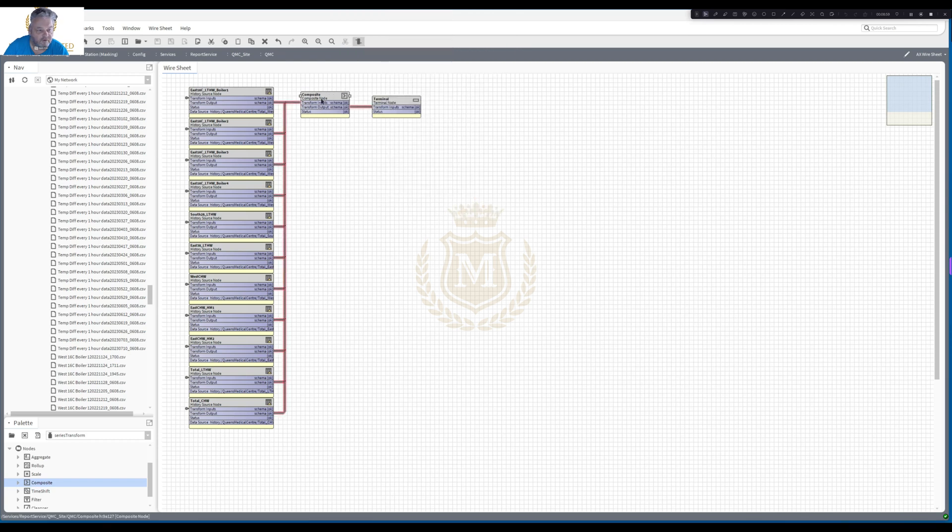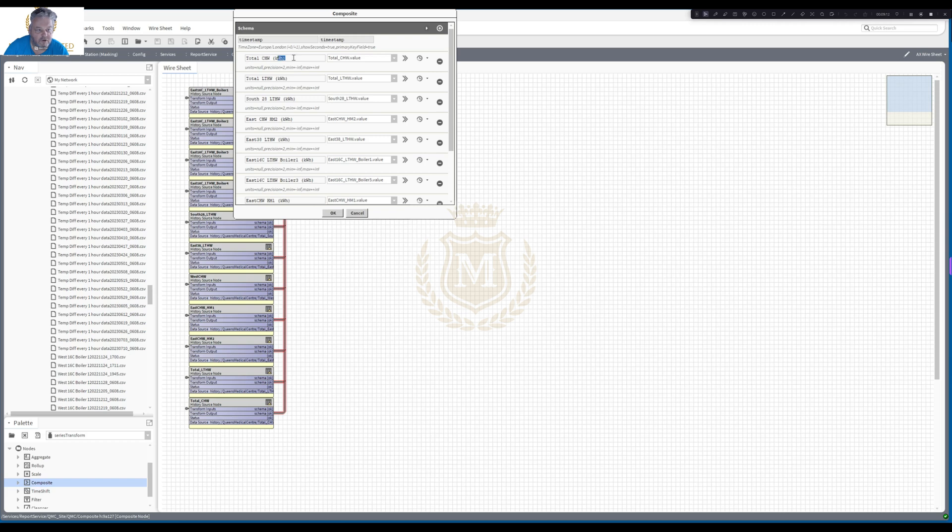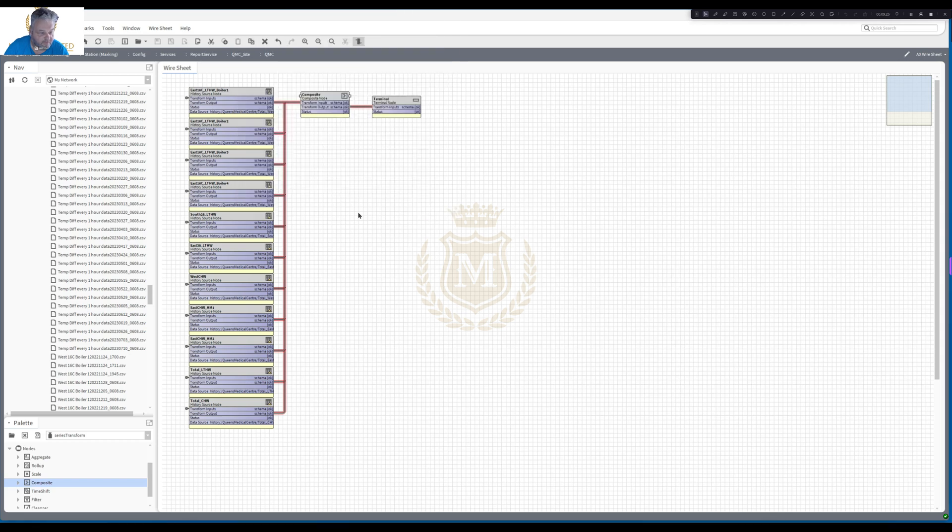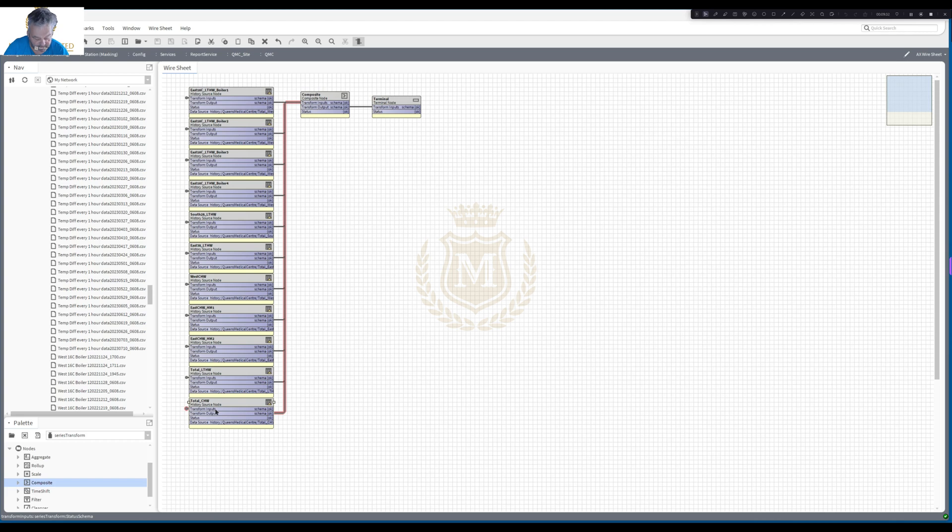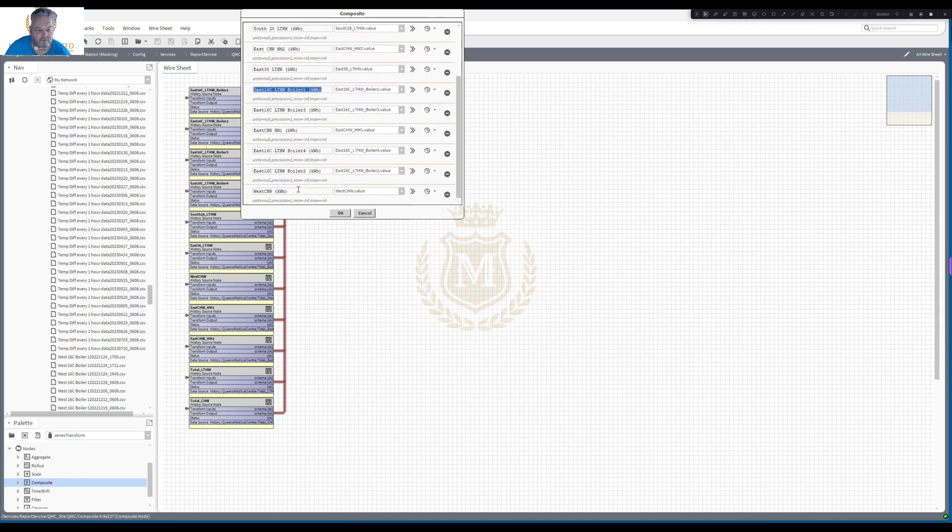So the composite one. If I open up this, so we've got, you can change this text to whatever you want it to be. You don't have to have kilowatt hours in brackets. Or you can take it out. Or you don't have to have total. You put your own text in there. But the value is what you want to display from the history. And you will pick up that value. So total chilled water dot value. That is from, where this is from. Total chilled water. It's from this node here. From there. So you put in all your history values. You put your own text in of what you want. And then you go OK.